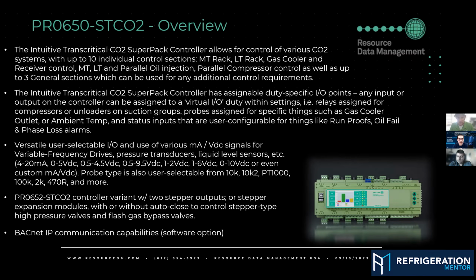I think that's important because what people need to understand, I talk to them a lot, and like I said, a lot of different controller manufacturers, the same things happening with them as well. There needs to be this recommissioning or fine tuning after the store is installed as well, because I've seen this tons and tons of times going out with an OEM to a site and they haven't been there for 3 or 4 months after the store has been started up, and we get into the controller and look at the controller and nothing has been fine tuned to that actual system or that case. They're just using the defaults, right? So that's really important. Thank you, Cody, for that.